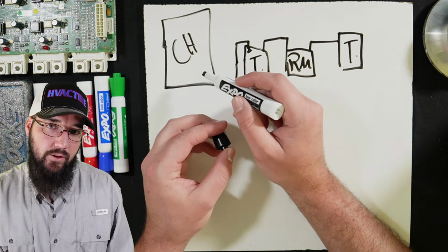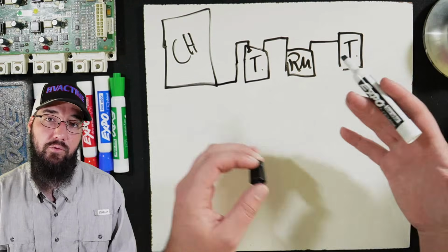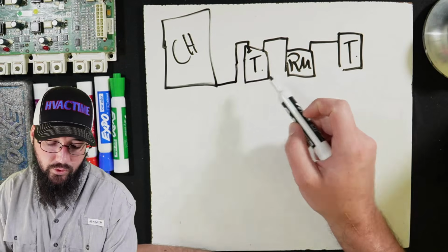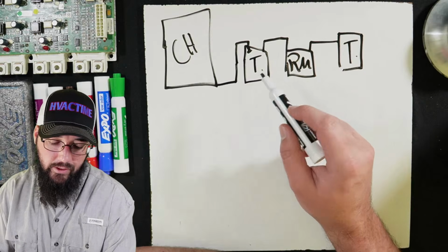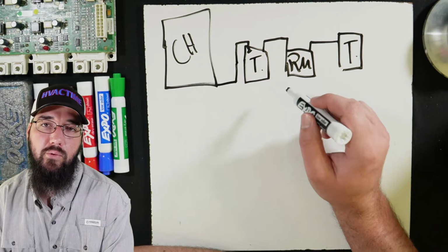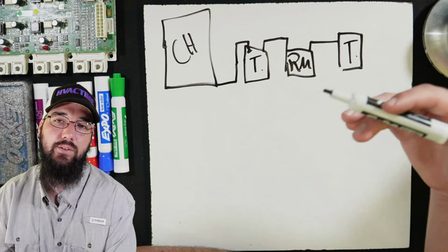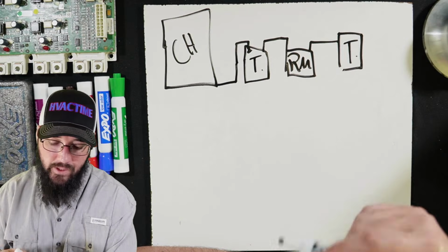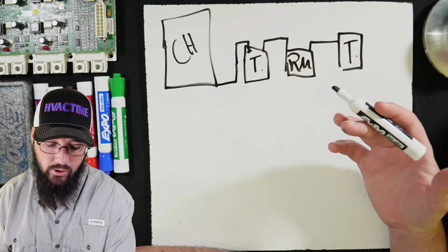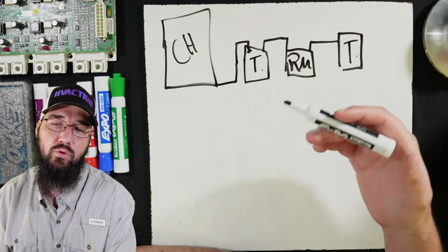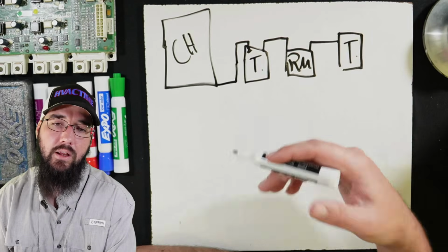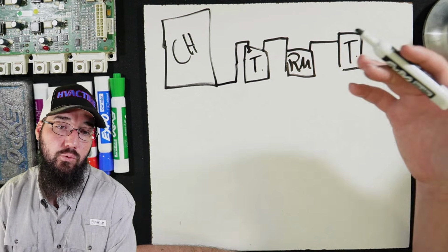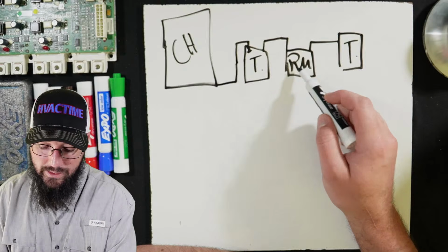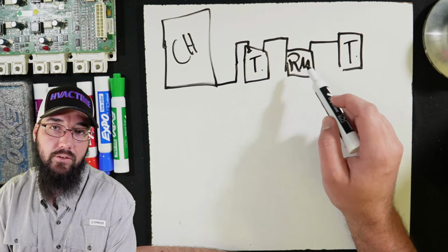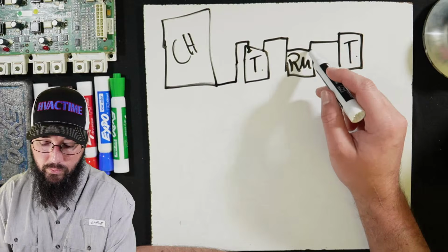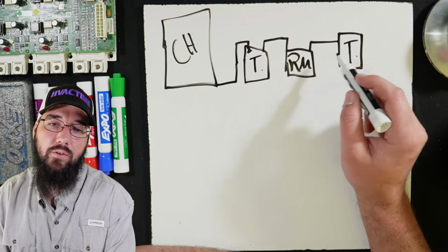Those are going to get stuck in there while you're trying to get the vapor refrigerant out. So that is where there is a strong argument for the pull method over, let's say, a push-pull method. And there is debate on how effective push-pull really is on increasing throughput compared to pull. So one of the keys that makes pull work is we have to use a subcooler on the vapor side.